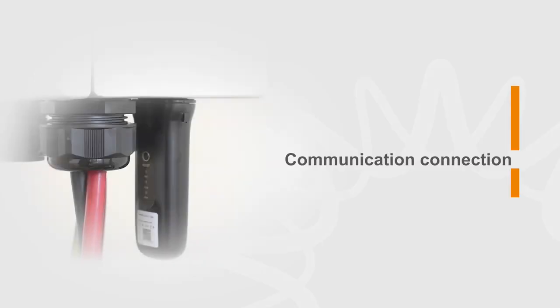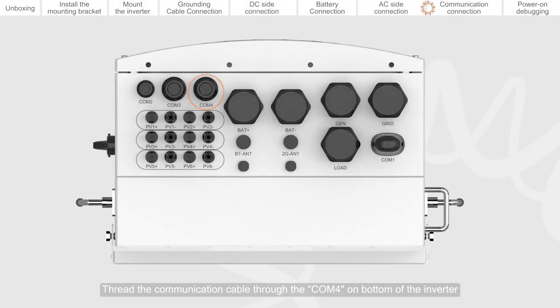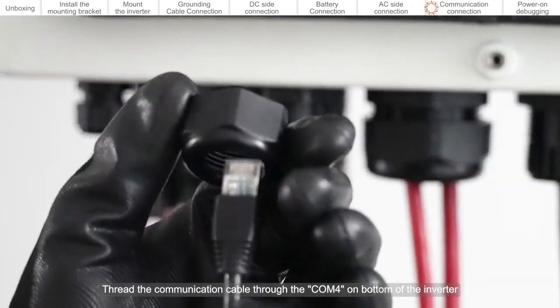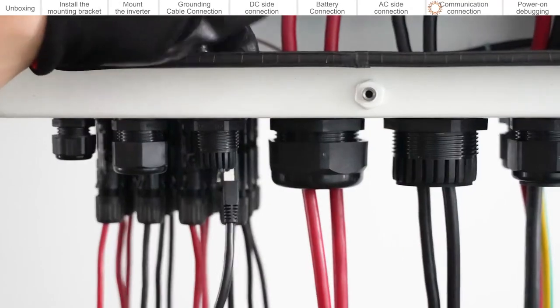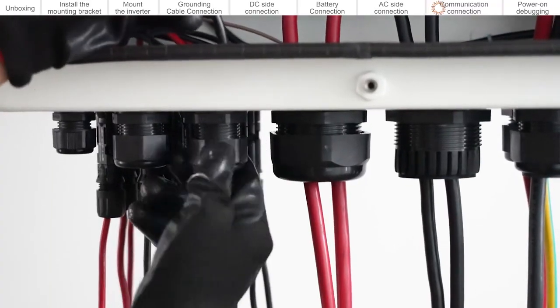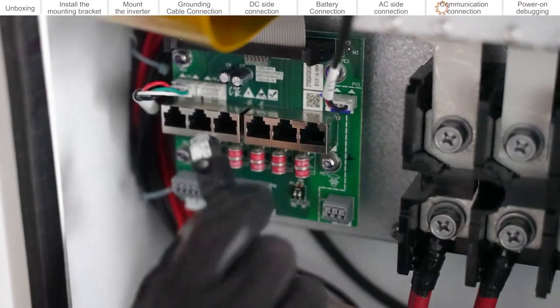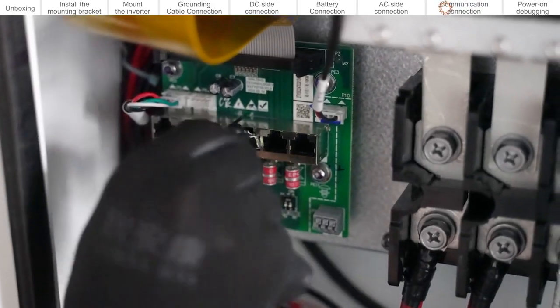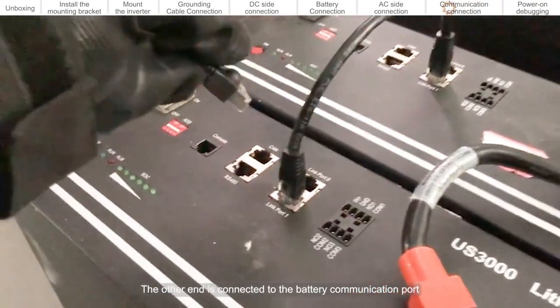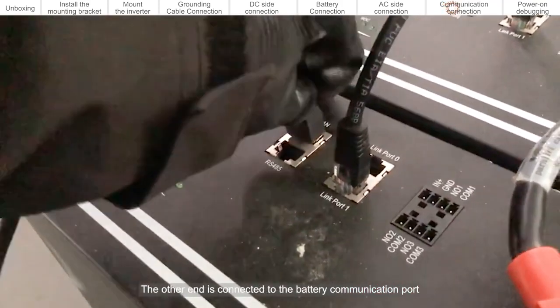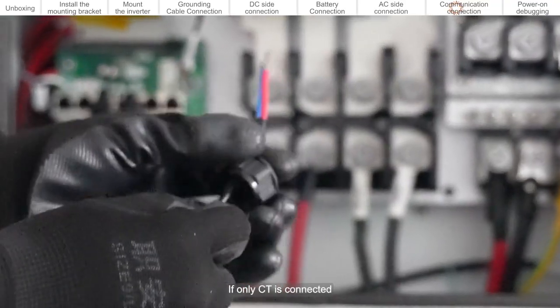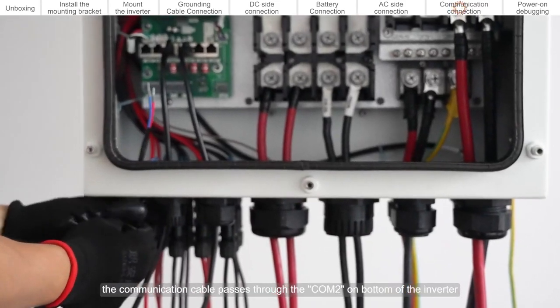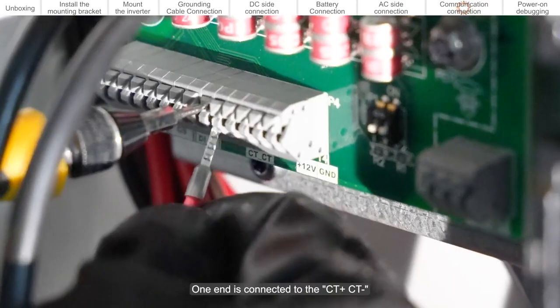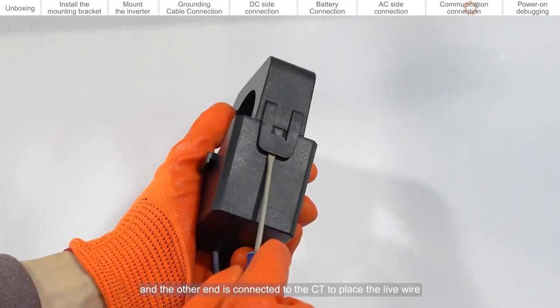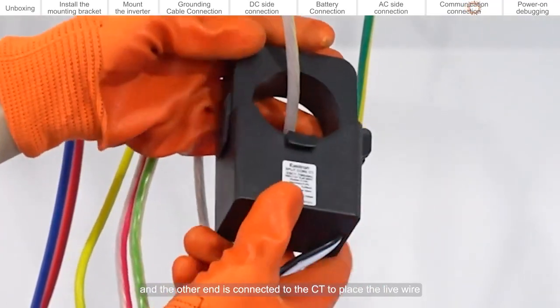Communication connection. Thread the communication cable through the COM4 on the bottom of the inverter. One end is connected to the BMS port. The other end is connected to the battery communication port. If only CT is connected, the communication cable passes through the COM2 on the bottom of the inverter. One end is connected to the CT plus, and the other end is connected to the CT to place the live wire.